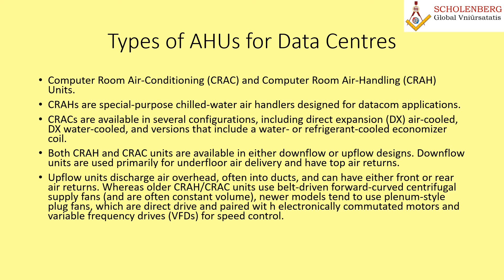Now let's discuss the air distribution within the data centers. How does it happen? Traditionally, the telecommunication spaces had no raised floor and used overhead ducted delivery, whereas datacom facility centers use a raised flooring system as a supply air plenum. There are two ways in which the air delivery or air distribution happens. One is underfloor air delivery and the second one is overhead air delivery.